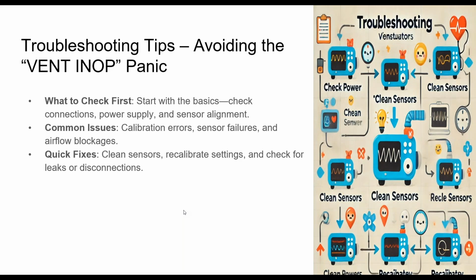But when you get a vent in-op, which is probably one of the worst errors to at least flash on a screen that I've ever seen, or a similar issue that says something is causing harm or potential harm to your patient, you want to do a couple of things. Check the basics. Check to make sure that your connections for your tubing are intact. Check to make sure that there are no leaks in the system.